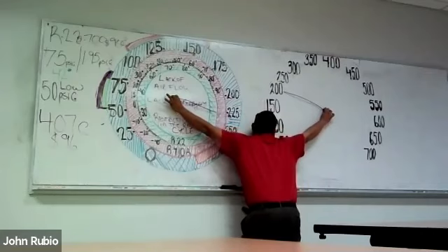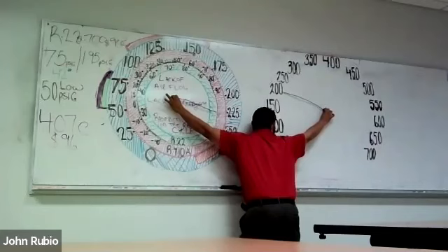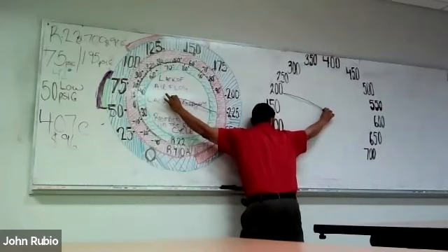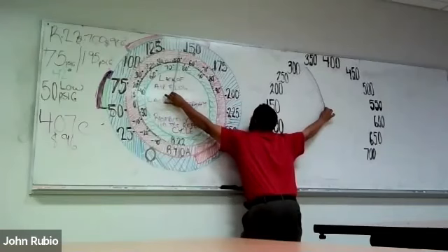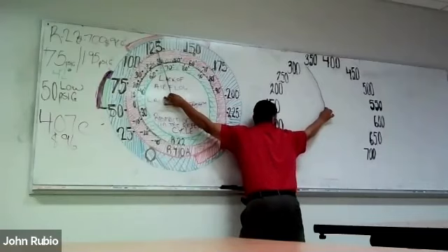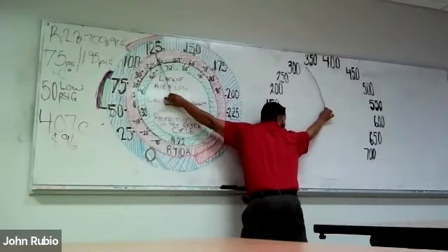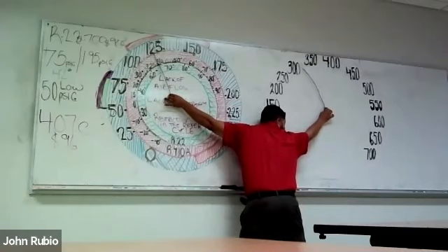And also, again, the numbers. In the case of equalized, look at gauge pressure. How close are they? These are equalized pressures. They're way closer than 125 over 300. Meaning that when these turn on, this needle rises, this needle drops, and they simmer out and meet right about there. Do you understand? When the system is truly low on refrigerant, your high side needle will be congruent. If your high side needle is not congruent, you are not low on refrigerant. Either your evaporator has ice on it or you are in a restricted state.